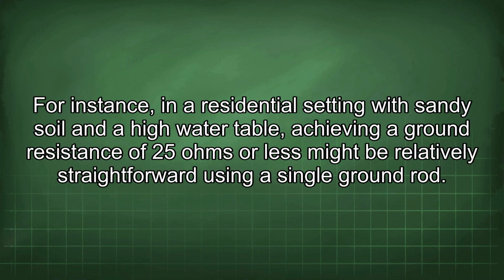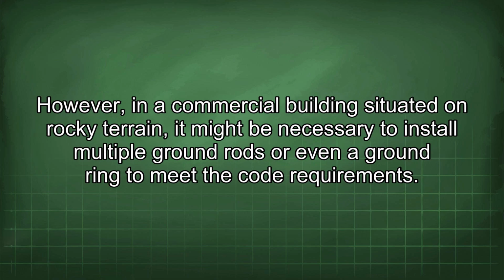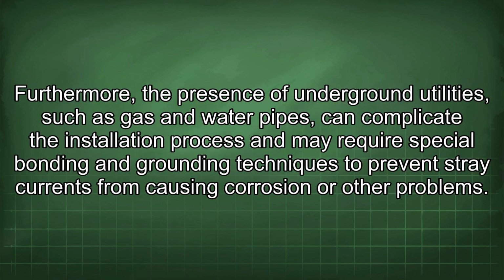For instance, in a residential setting with sandy soil and a high water table, achieving a ground resistance of 25 ohms or less might be relatively straightforward using a single ground rod. However, in a commercial building situated on rocky terrain, it might be necessary to install multiple ground rods or even a ground ring to meet the code requirements. Furthermore, the presence of underground utilities, such as gas and water pipes, can complicate the installation process and may require special bonding and grounding techniques to prevent stray currents from causing corrosion or other problems.